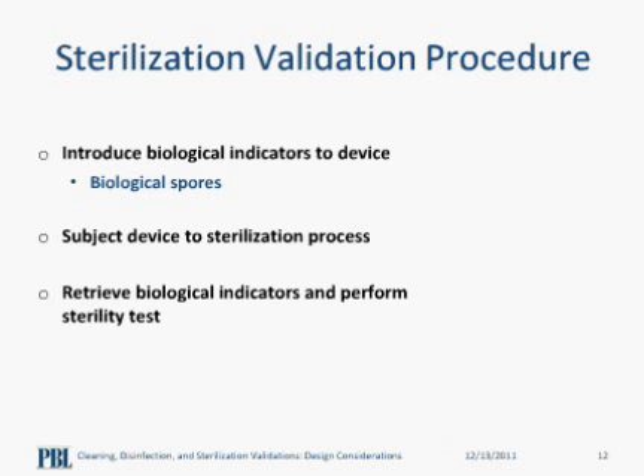The way we validate the sterilization procedure is as follows. First, we introduce biological indicators to the device, typically consisting of bacterial spores. We then subject the device to the recommended sterilization process, for example, autoclaving, and then we retrieve the biological indicators and perform a sterility test.